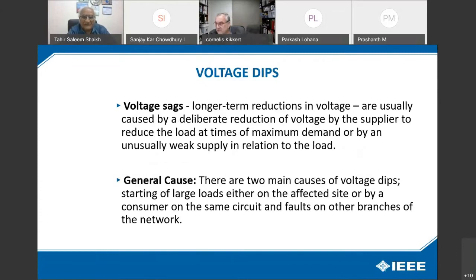Voltage sags, a longer-term reduction in voltage, are usually caused by a deliberate reduction of voltage by the supplier to reduce the load at times of maximum demand, or by an unusually weak supply in relation to the load because of load shedding. What we call it is load shedding. As a general cause, there are two main causes of voltage dips: starting of large loads, or transients because of large loads, either on the affected site or by a consumer on the same circuit, and faults on other branches of the network.